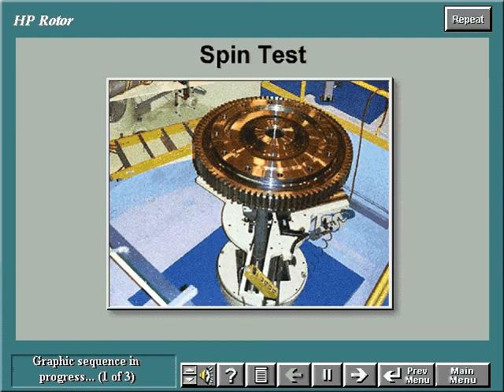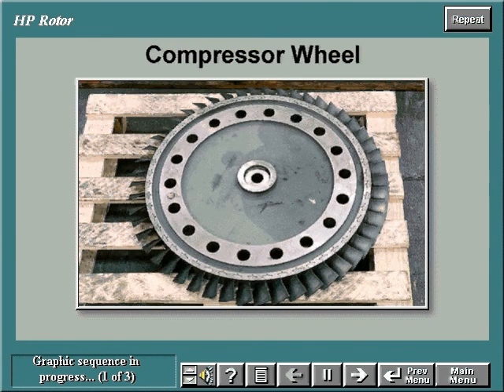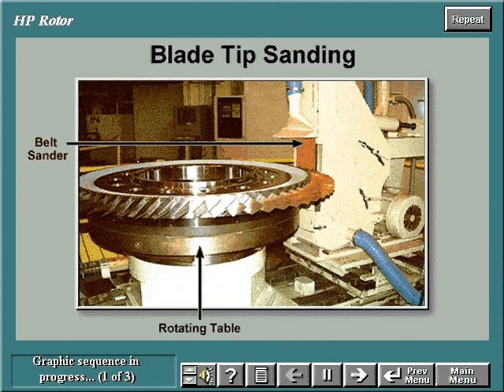Prior to assembling the high pressure rotor, the compressor and turbine wheels are spin tested. Then the compressor blades are slid into slots in each compressor wheel. The blades are staked to maintain their positions in the wheel. Once assembled, each compressor wheel is placed on a rotating table and a belt sander sands the blade tips down to the proper dimensions as called for by specification.